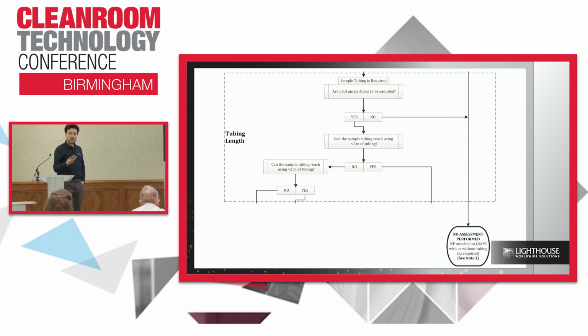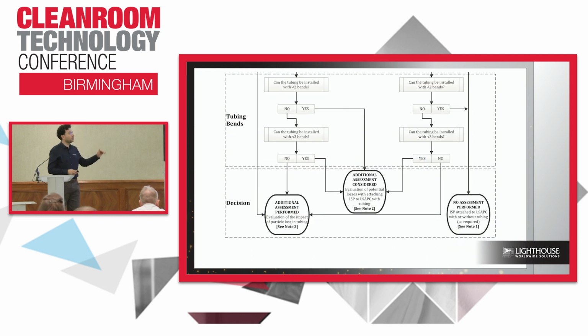If you can do it, okay, what kind of assessment do you need to consider? I have one example that I will go through in detail. I just want to show you that after the tube length, we have these tubing bends, and then the decision. The decision takes you to notes number 1, 2, and 3. Number 1: no assessment performed, but we still give you some guidance in terms of how you will maintain your system, because we all know that even when you do direct sampling, there are things that you need to consider. And note number 2: there is an additional assessment that you need to consider, because there is a risk at a certain level which will be acceptable in some applications and not in others. So if it's not, then an additional assessment is required.